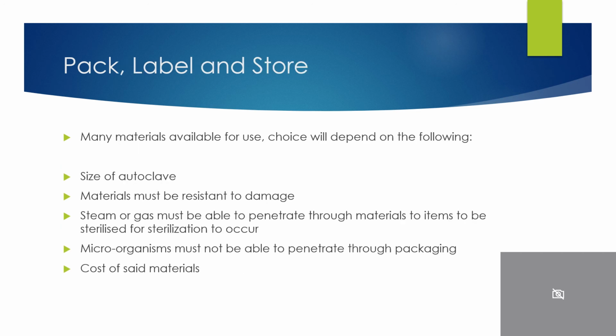Pack, label and store. Many materials are available for use. Choice will depend on the following: the size of the autoclave. Materials must be resistant to damage. Steam or gas must be able to penetrate through materials to the items to be sterilised for sterilisation to occur. Microorganisms must not be able to penetrate through the packaging, and also the cost of said materials is very important from a practice point of view.